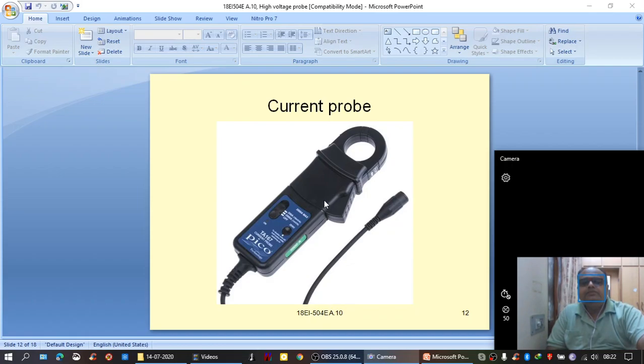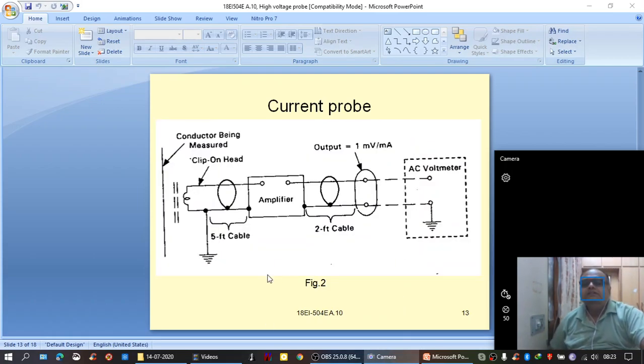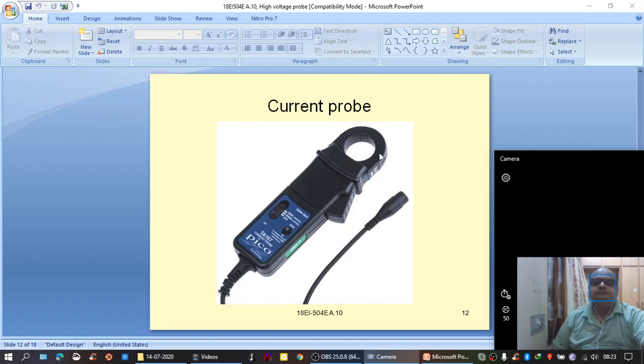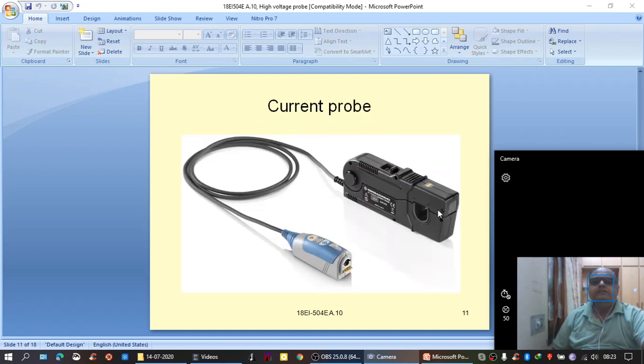Instead of opening the circuit, directly the current can be measured. Something like this. Just press this, the clamp will open here, and the wire across which the current is to be measured is placed inside, and this is connected to a meter or measuring device. Current would be directly measured. And of course, a scaling also is available here, into 1, into 10, into 100. That scaling also would be there depending upon the magnitude of current to be measured. Now see, the internal circuit would be like this. Clip on head, that is this portion, this one.